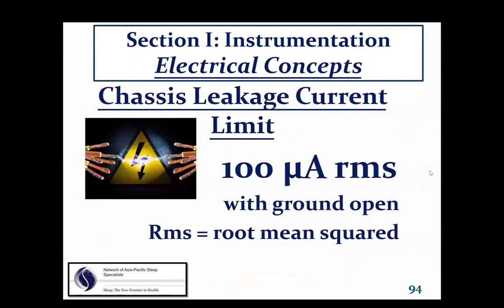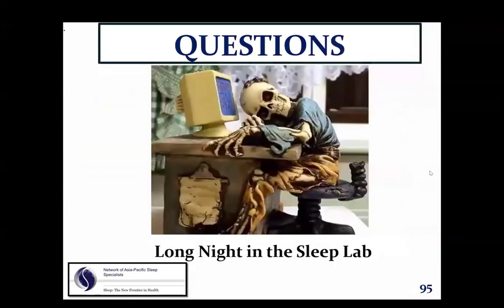The standard for chassis leakage current is it cannot exceed 100 microamps root mean squared with ground open. Now, that isn't important information for you to know because biomedical engineering has that standard. And it might be a little more, it might be a little less, but they control when they check the equipment, whether it passes or whether it fails. So nothing you need to know, but you need to know that we have to do the chassis leakage current test. And again, here's how we all look after a long night in the sleep lab.